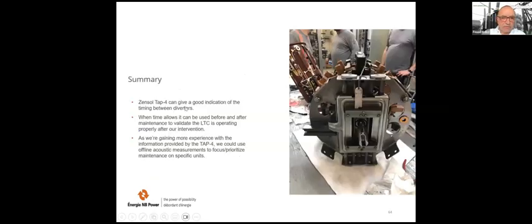So Zensol Tap 4 can give a good indication of the timing between diverters. When time allows, it can be used before and after maintenance to validate the LTC is operating properly after our intervention. As we're gaining more experience within the information provided by the Tap 4, we could use offline acoustic measurements to focus prioritized maintenance on specific units.